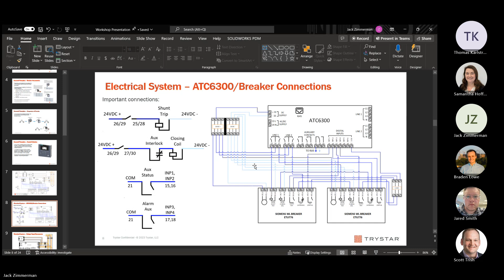So those are the main connections here. And note, there's a lot of wiring here. The reason it looks so much more involved than this is there's two sets of this, as well as terminal blocks. So we're not running all of these individually. We're just commoning up all of the 24 plus and minus and pulling it all from one big block. So that's why it looks complicated. The blue represents plus 24 volt DC. The blue-white stripe, or the light blue, is minus. And this is just a section of this main wiring diagram as well, just for reference.